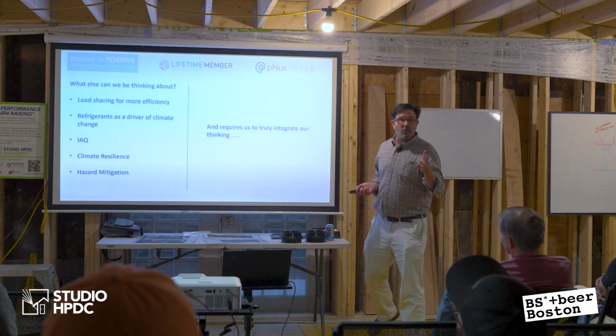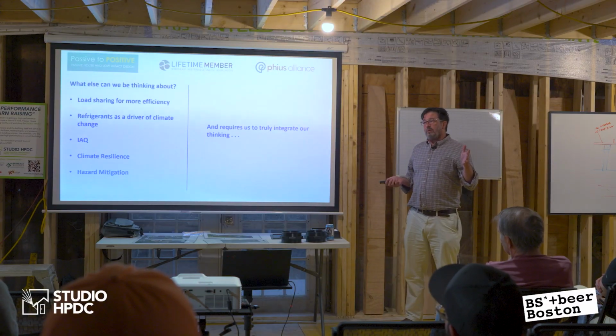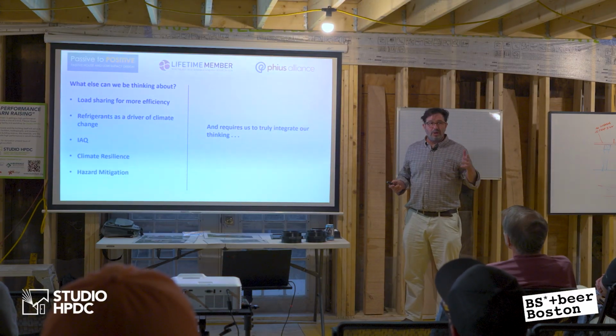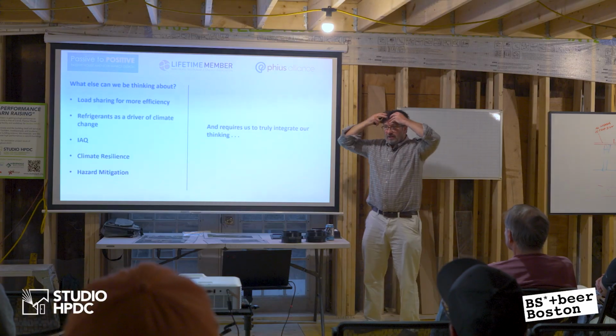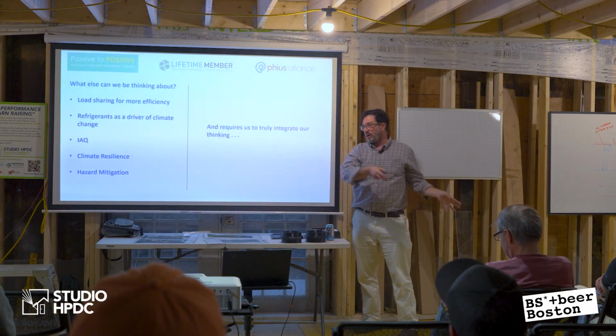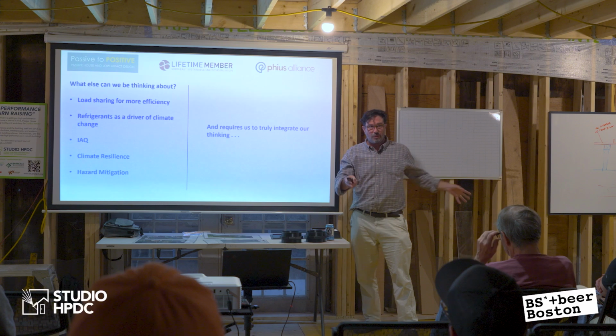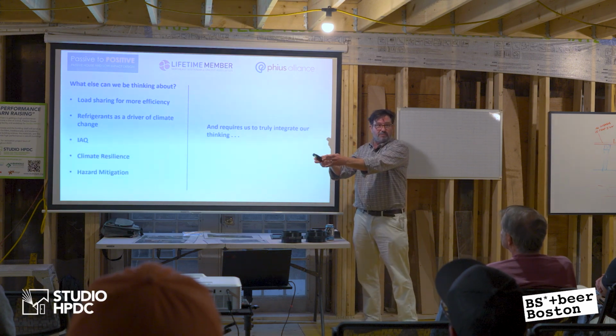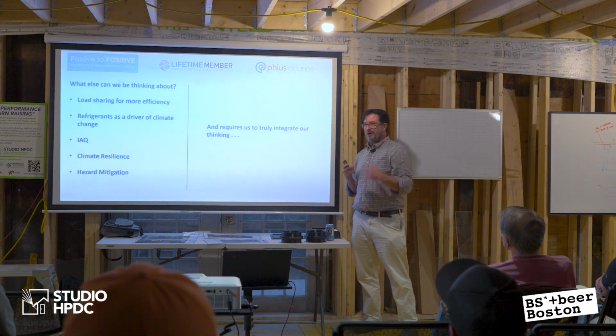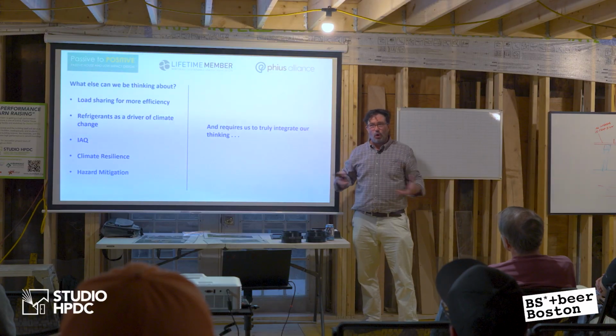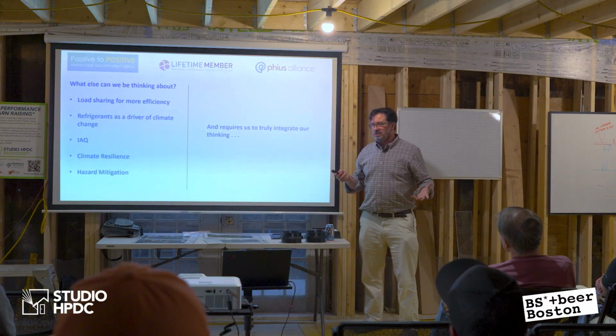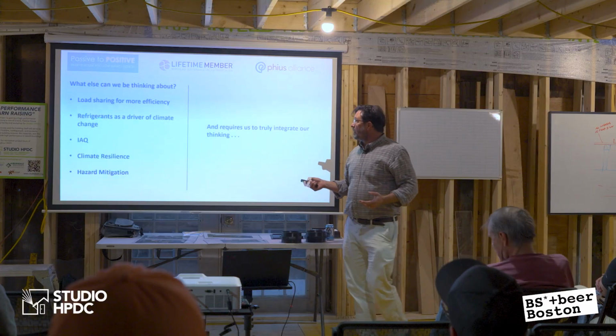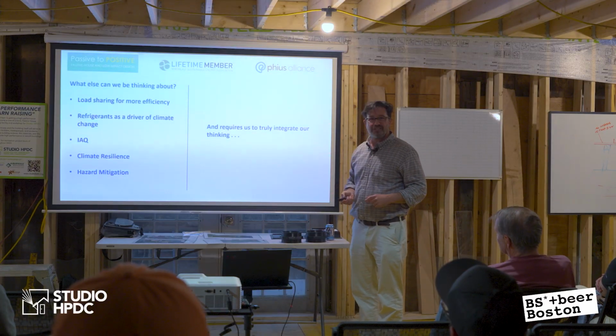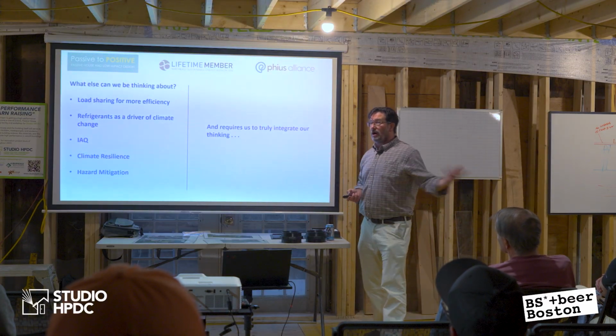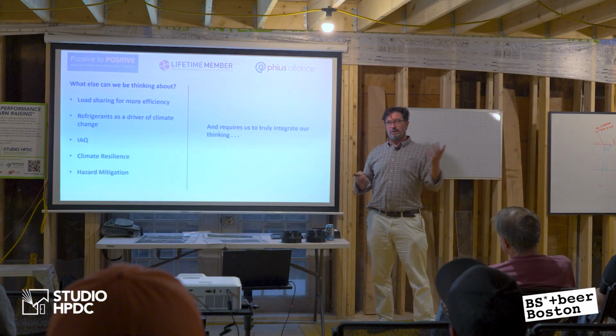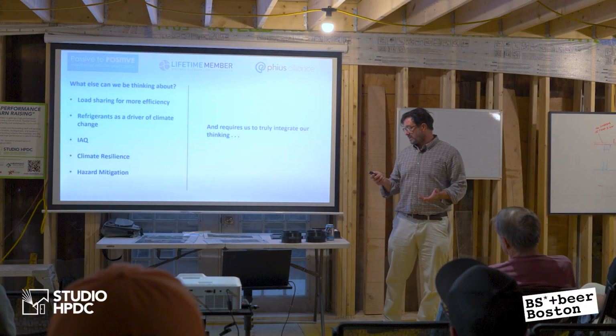All right, there are a few more things that I want to touch on. If I'm thinking outside of my limited model box by looking at hourly modeling, even though the certification standard does not tell me to, and he's thinking outside of his box of snapshot summer, snapshot winter, and we're trying to think holistically, which is what good teams do, then we might be able to talk about load sharing for more efficiency. Oh, you've got a hot water load and a low heating load. Oh, you've got a big cooling load. Hey, what about combining them and seeing what happens?